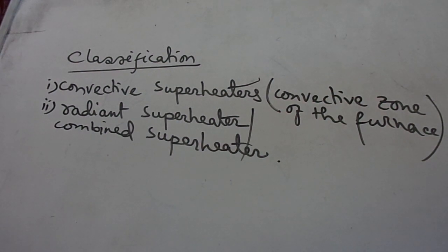Earlier designs screened the convective superheater from the furnace radiation by a bank of water-filled tubes, which not only protected them from combustion flames and high temperature, but also intercepted the slag particles and reduced the slagging problem. The convective superheaters are often termed primary superheaters, where saturated steam from the drum is admitted.